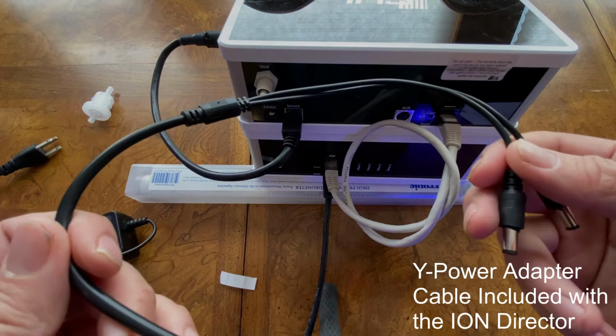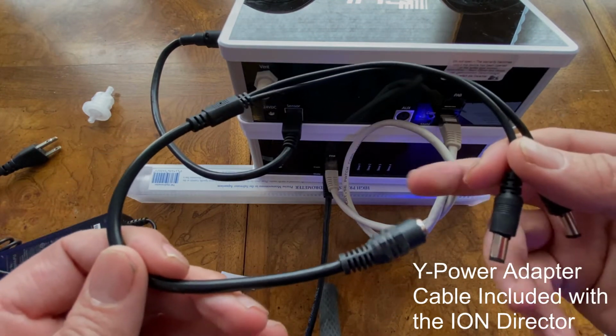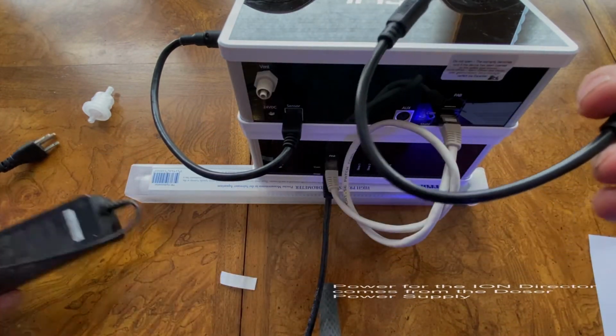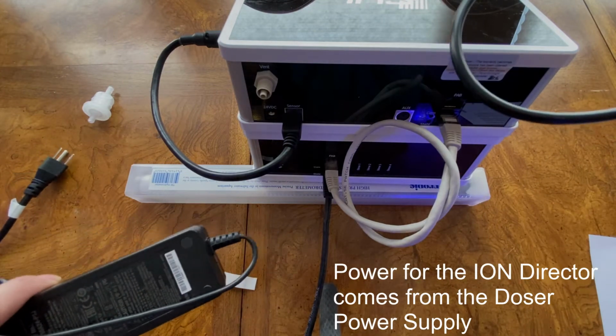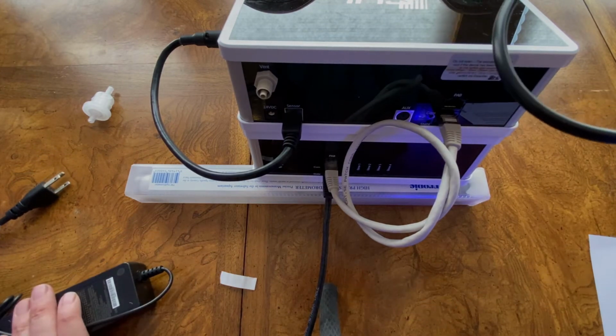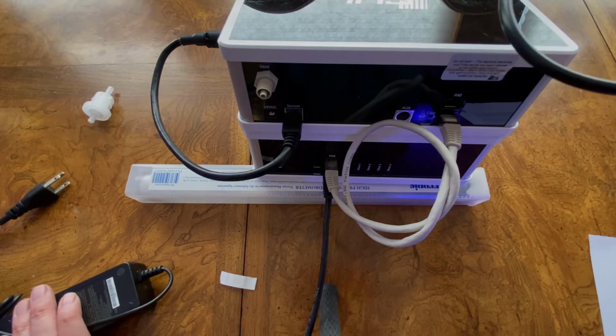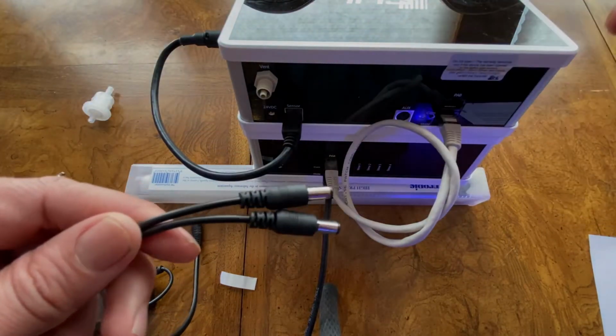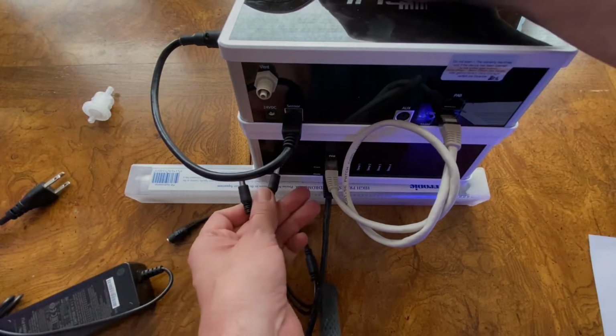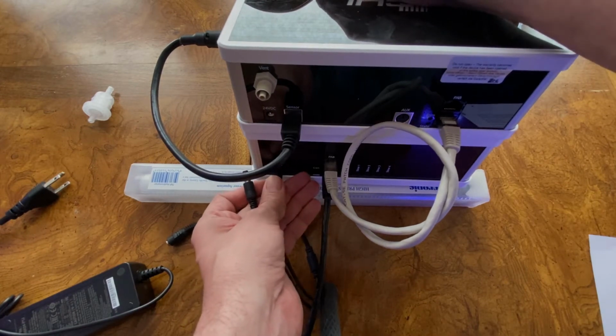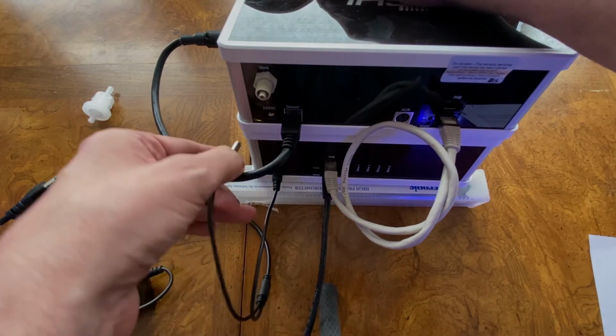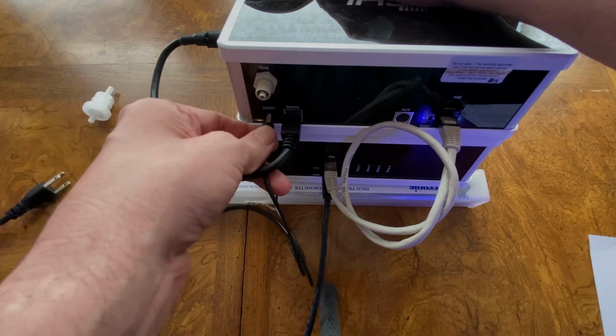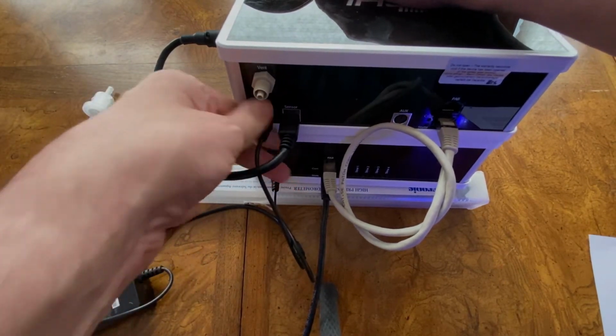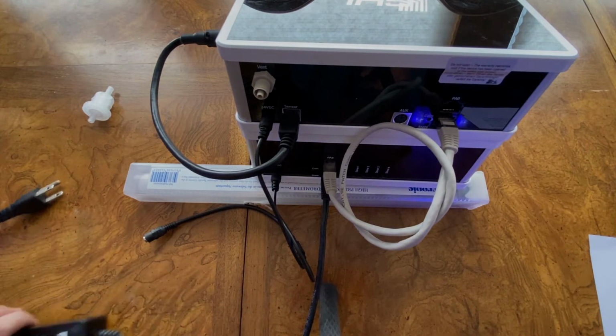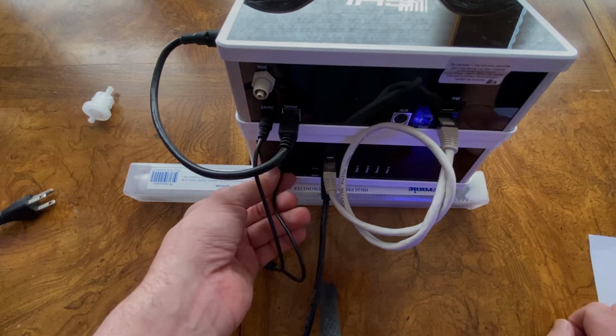You're going to get a Y cable just like this when you order your ion director. What this Y cable is for is that it's going to share the same power supply as the doser. And this eliminates having to have an additional power supply in the cabinet. So what you're going to do is take the side of the Y connection itself, and you're going to plug one into the doser, okay? And I like to go underneath, and one to the sensor. And then that's how you install the Y connection.